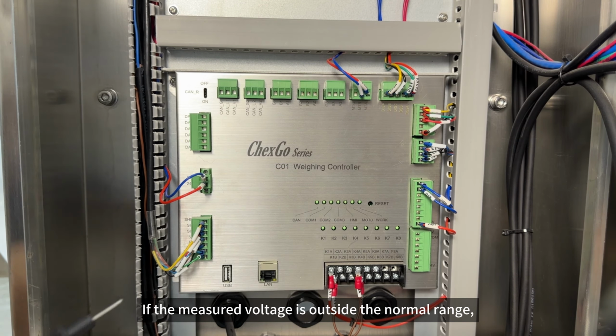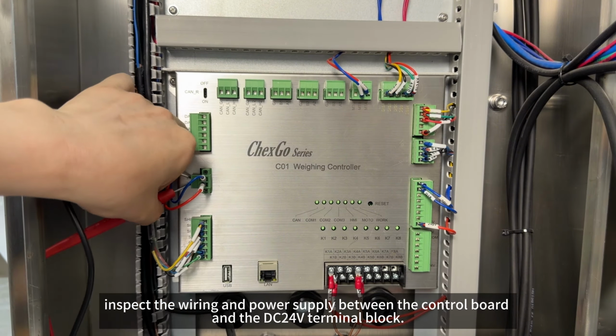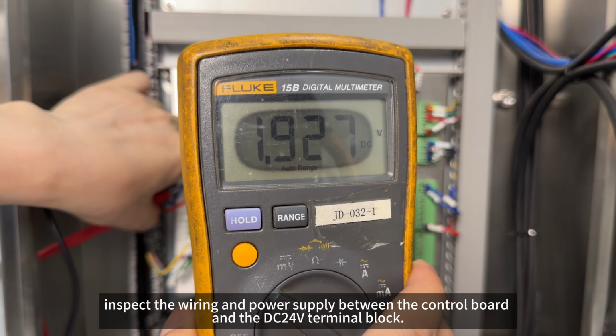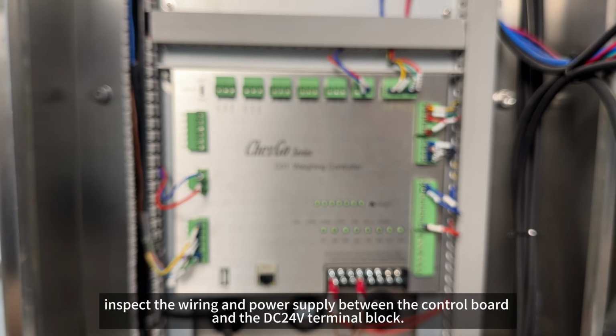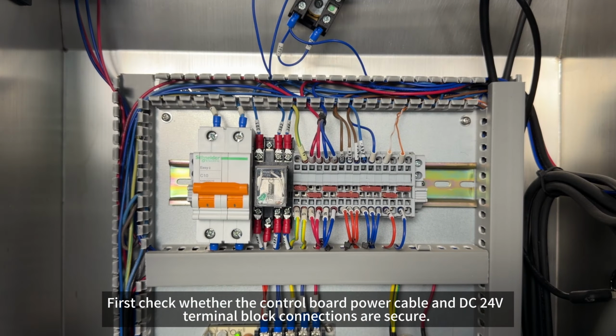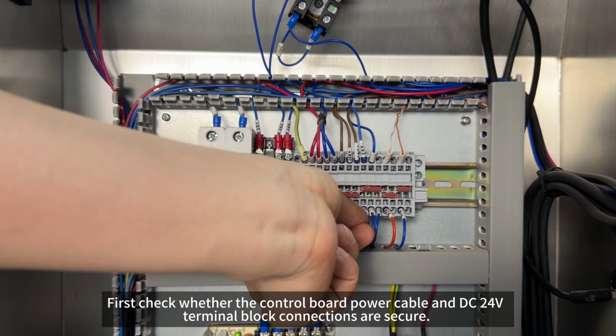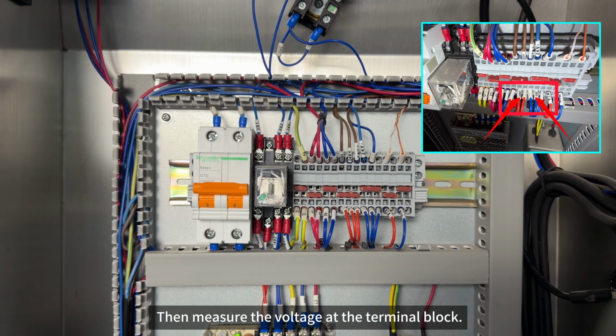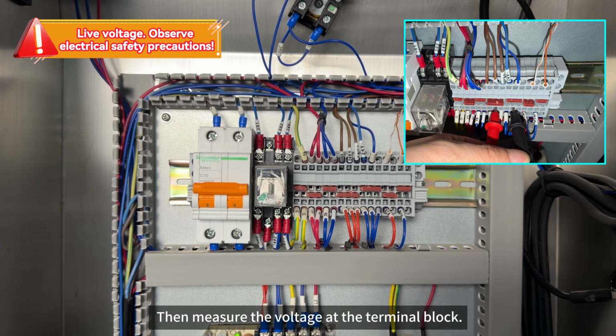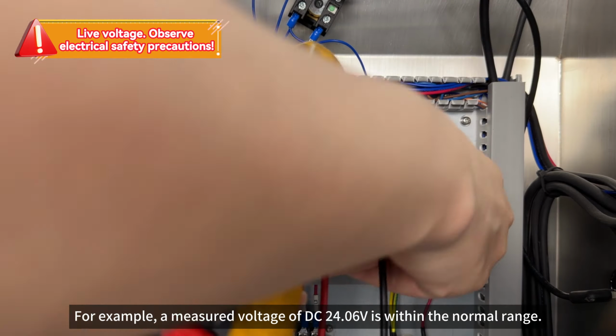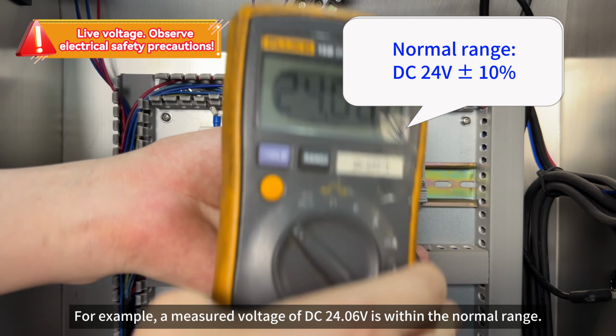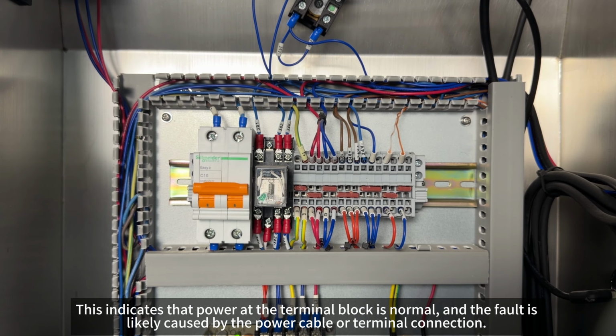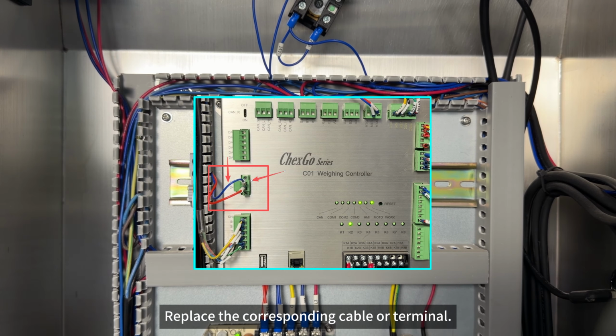If the measured voltage is outside the normal range, inspect the wiring and power supply between the control board and the DC-24V terminal block. First, check whether the control board power cable and DC 24 volts terminal block connections are secure. Then measure the voltage at the terminal block. For example, a measured voltage of DC 24.06 volts is within the normal range. This indicates that power at the terminal block is normal, and the fault is likely caused by the power cable or terminal connection. Replace the corresponding cable or terminal.